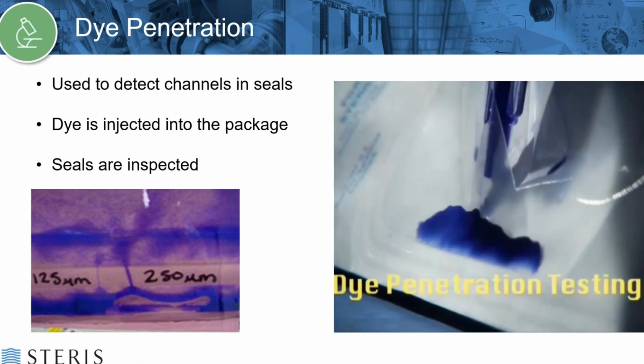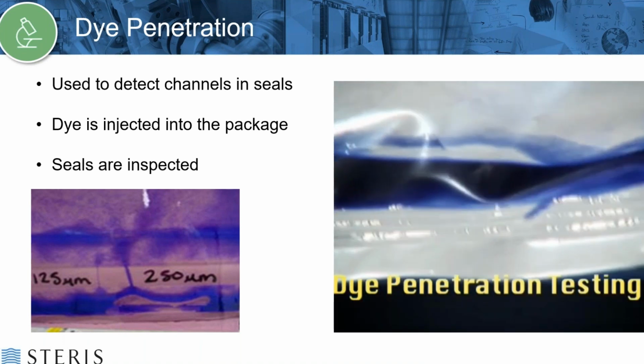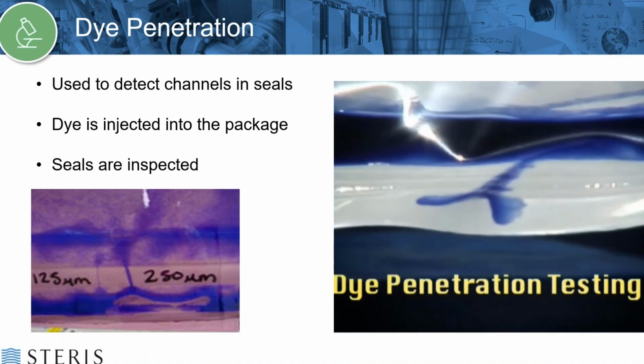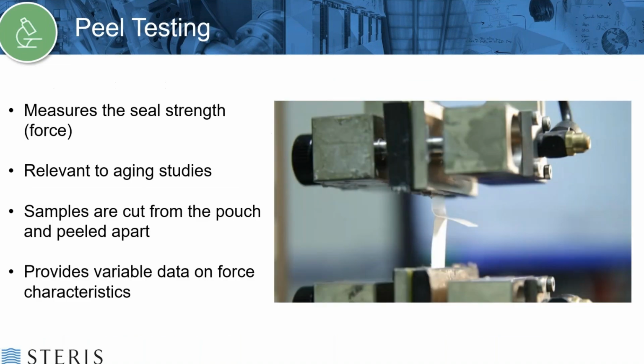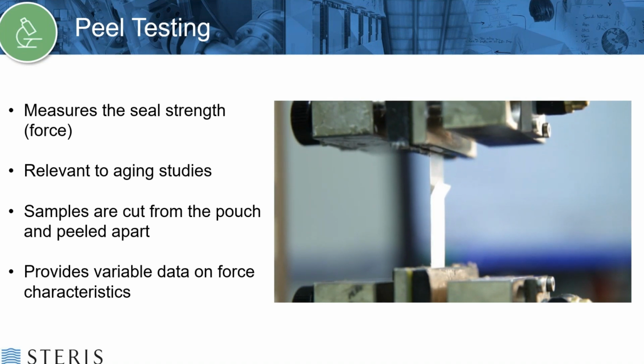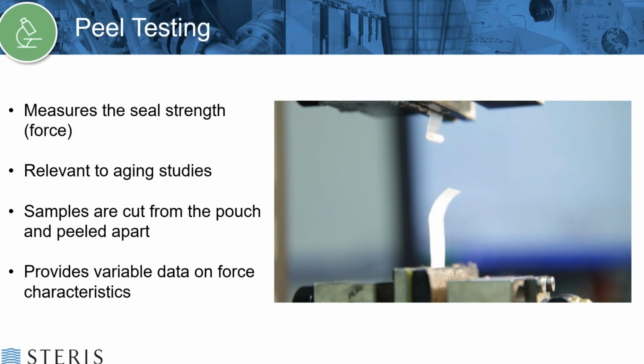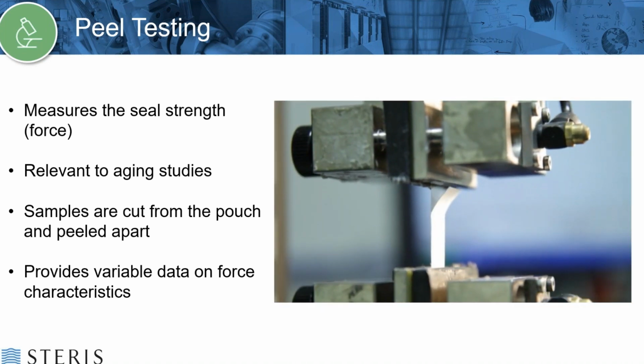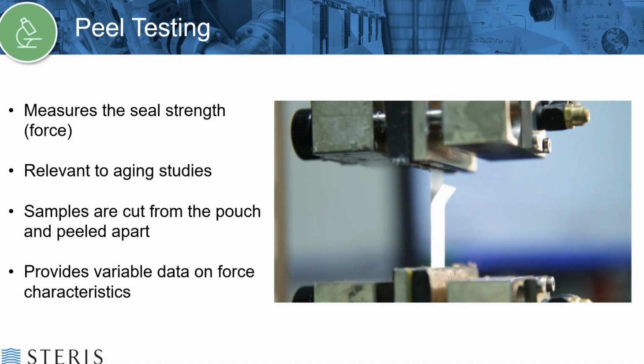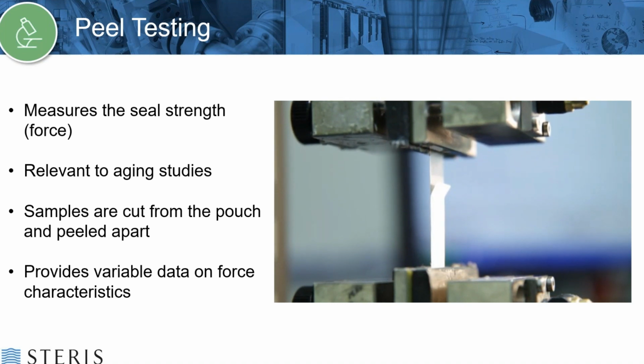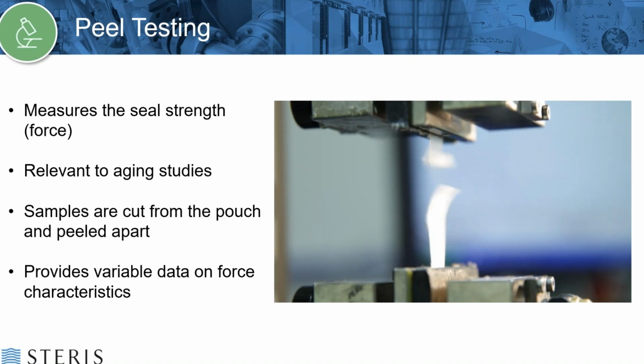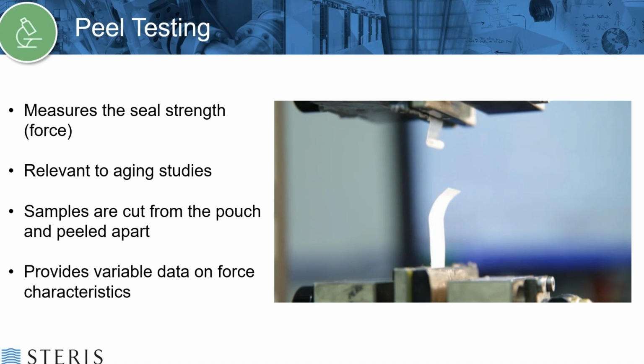So here's some dye penetration. Again, you can see we inject that purplish blue dye, and you can see that channel clearly through the seal area of that pouch, indicating a breach of that package's integrity. And here's peel testing. Again, this is a segment of one of the sides of a package that has been cut out and then pulled and the force measured. So this one's nice because it gives you some variable data, so quantitative data that you can do some statistical analysis on, whereas the integrity tests are more of a qualitative pass-fail type test.